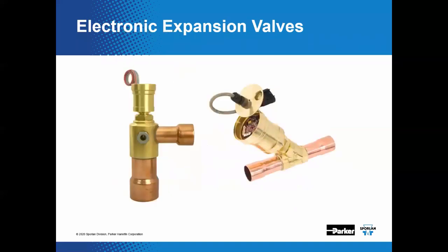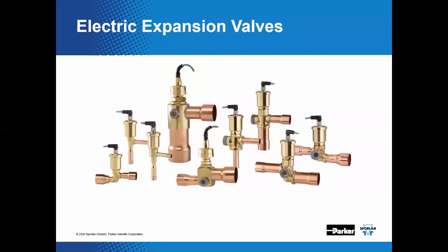Awesome. Now, something that continually comes up, and I actually failed to discuss it on that previous slide. Inevitably, everybody refers to these valves as electronic expansion valves. Whereas back here on this slide, the bulk of those valves are actually electrically actuated. They don't have any control mechanism built into the valve. They're relying on a separate controller to tell them what to do. And so in that situation, they're simply an electric expansion valve.